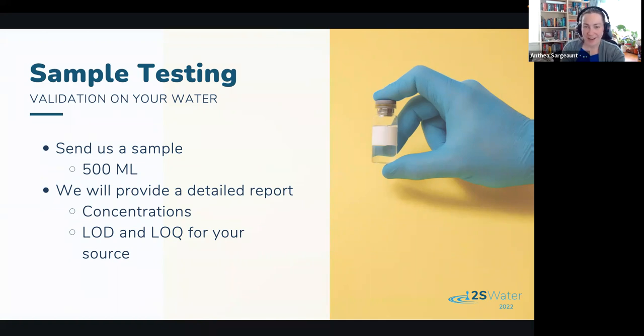Michael has a couple questions for me. Do we have testing for TSS in treated water? Again, our system does not actually do TSS testing - we do total dissolved solids. Do we have testing for arsenic in water? Yes, we can detect arsenic in water. Right now arsenic is one of a suite where we have a slightly higher detection limit than we'd like. We know what to do to get it down there, but as a startup, the world is a list of priorities. So we do have arsenic detection in water, and I'd love to talk to you about what specific levels you're looking at so we can tell you if we're in the range you need, or if we need to keep working a bit more.